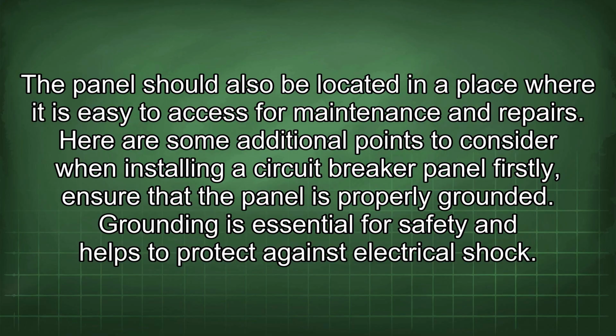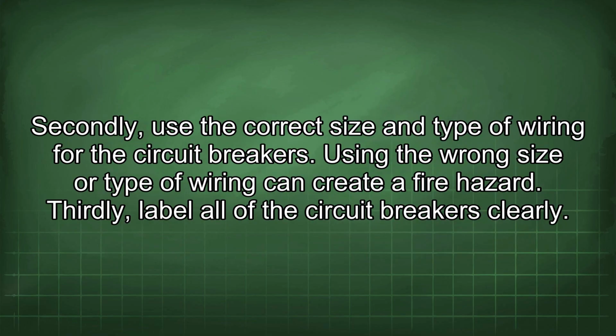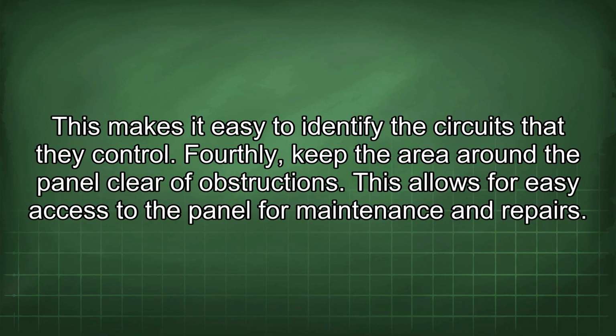Firstly, ensure that the panel is properly grounded. Grounding is essential for safety and helps to protect against electrical shock. Secondly, use the correct size and type of wiring for the circuit breakers. Using the wrong size or type of wiring can create a fire hazard. Thirdly, label all of the circuit breakers clearly. This makes it easy to identify the circuits that they control. Fourthly, keep the area around the panel clear of obstructions. This allows for easy access to the panel for maintenance and repairs.